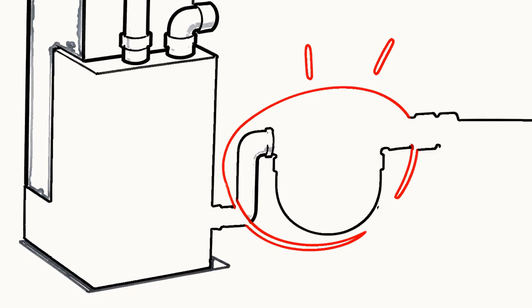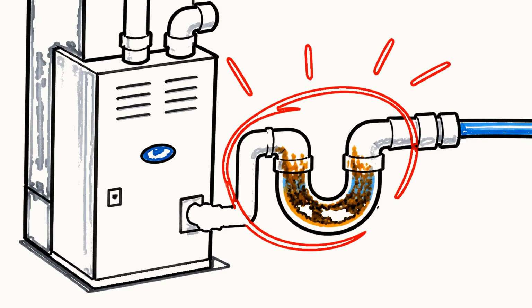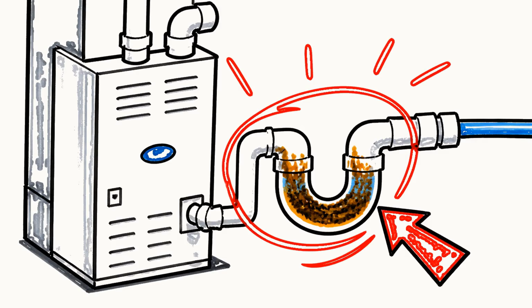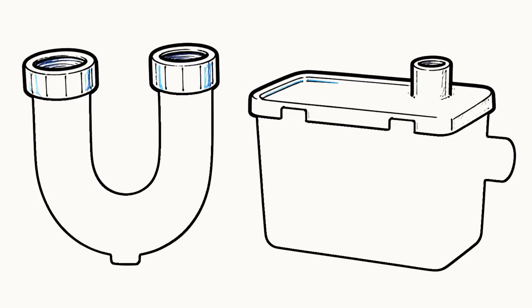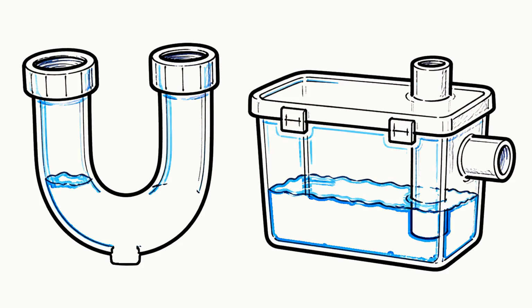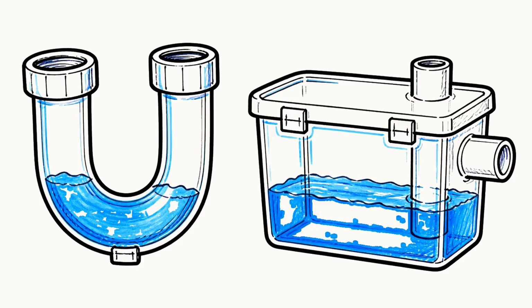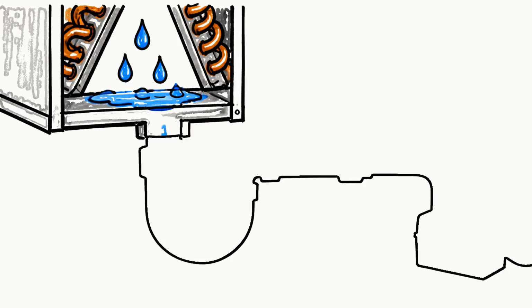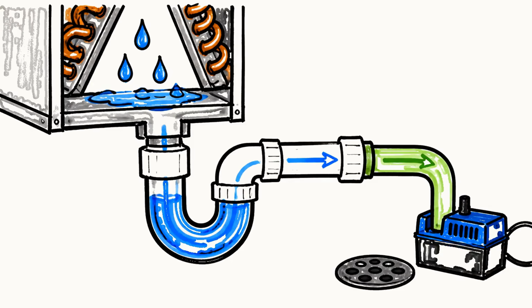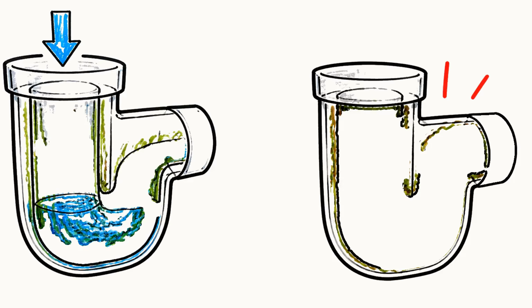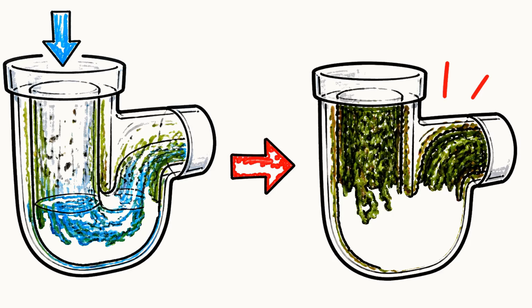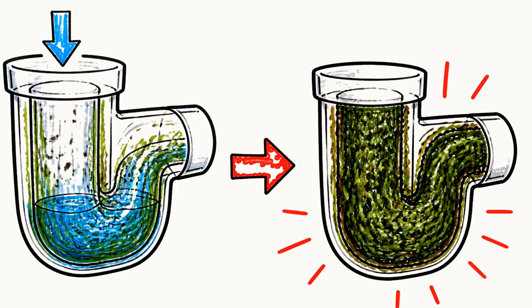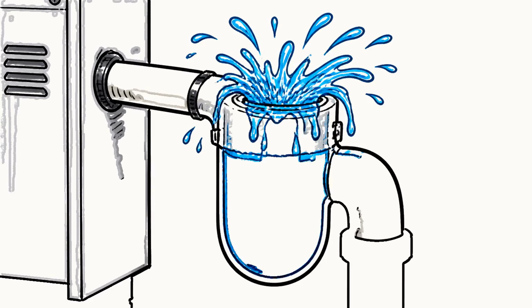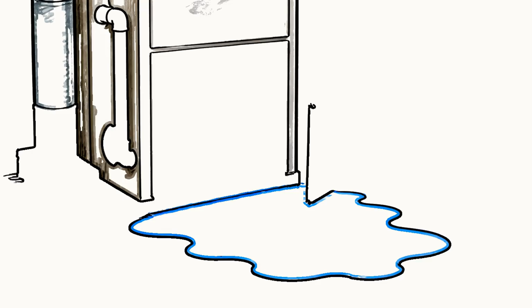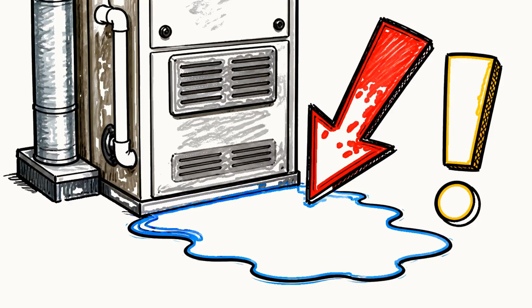Let us start with the high-efficiency furnace, the white PVC one, because that is where most of these leaks come from. The number one cause, by a wide margin, is a clogged condensate trap. Somewhere under or beside your furnace, there is a small plastic piece, sometimes a U-shaped bend, sometimes a little clear or white box. That trap catches the water coming off the heat exchanger and routes it toward a floor drain or a pump. The water it carries is slightly acidic, and over a season or two it grows a layer of slime, algae, and dust that eventually plugs the trap solid. When that happens, the water has nowhere to go, so it rises up and pours out the top. If your furnace is running and a puddle is spreading from the base, this is your first suspect.